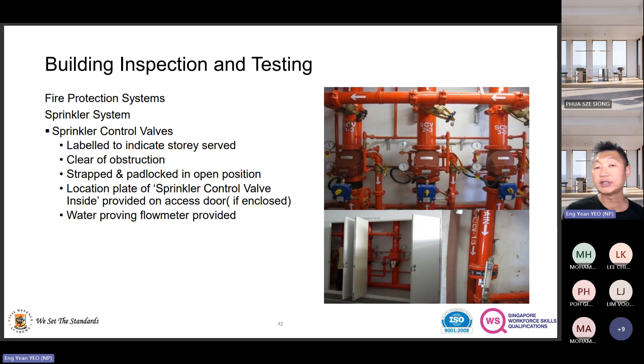So what they do at the control valve area, firstly, is make sure that when they're on this control valve, that one particular control valve must give enough water, right? Because when they fight fire, there are only two key components. One, make sure I have enough water to fight the fire. That's what the design intends. Next, after you reach the 30 liters per second, then the QP, you want to see where the pressure is. I want to make sure the pressure is recorded down. Then you look at the nameplate. Is it higher than the nameplate pressure, which is the minimum pressure? So the pressure that you see on the actual testing must be higher than whatever pressure is indicated on the nameplate. All right.